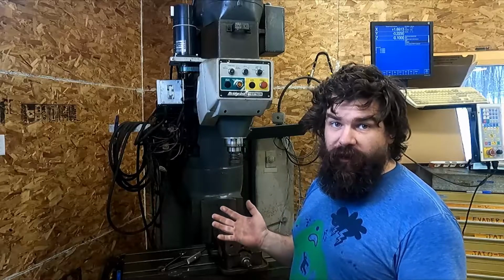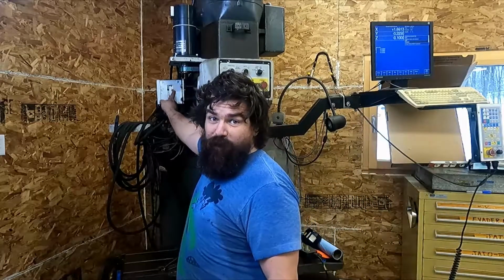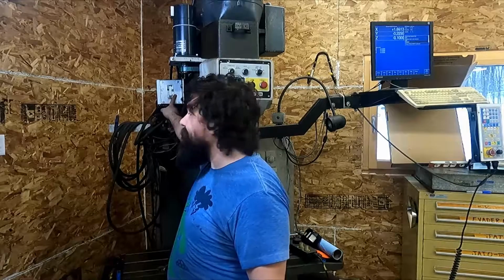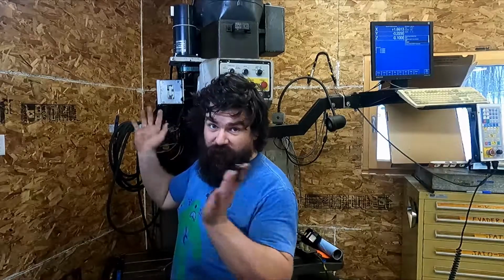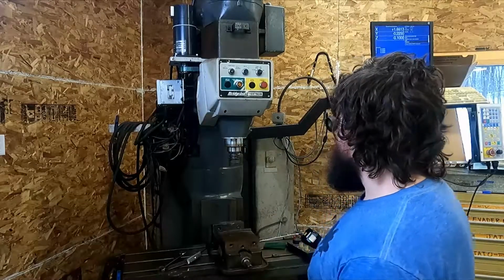We played around with acceleration and deceleration, and we actually got some smoke to come off the burnt oil on the braking resistor, which is fine. We didn't go aggressive with it. We just left it at just a little bit of smoke coming out the top.